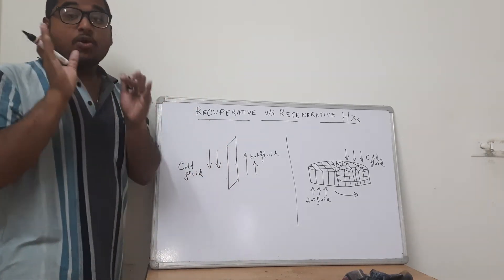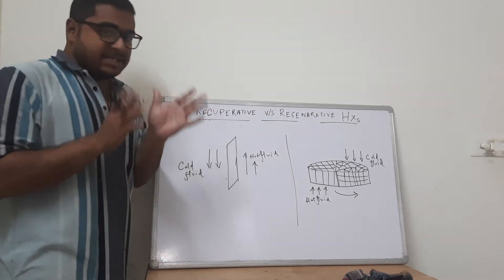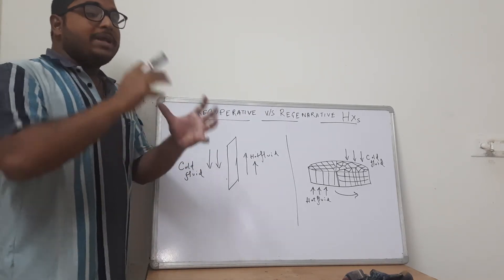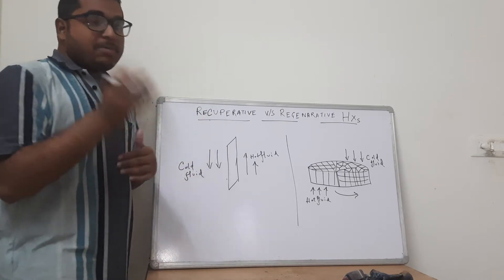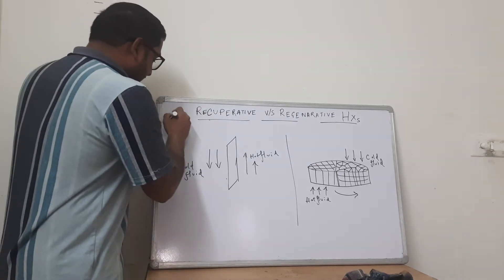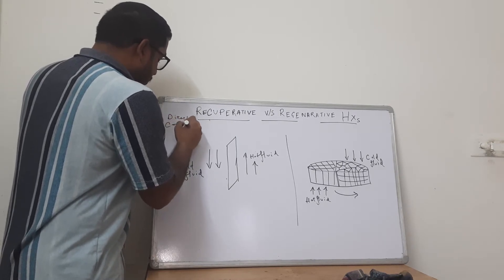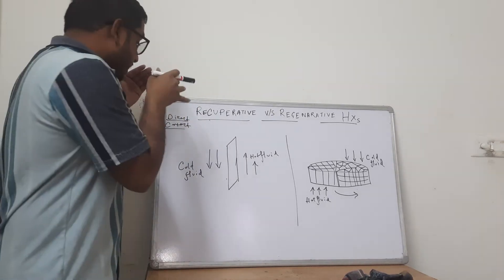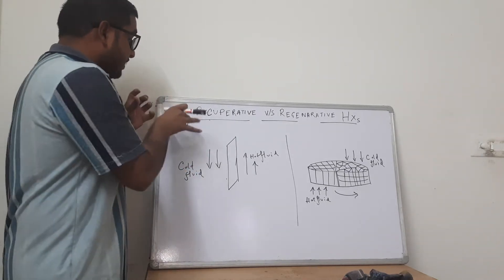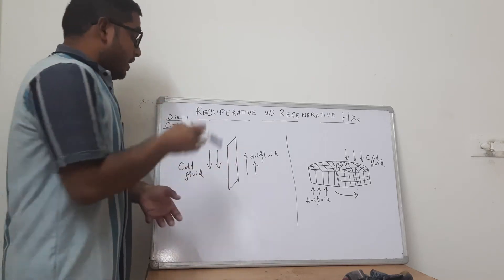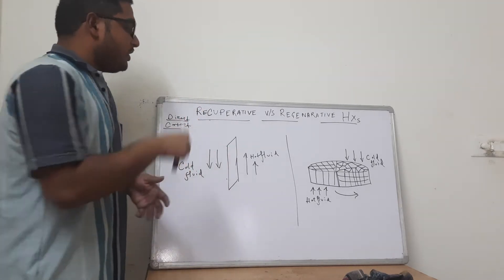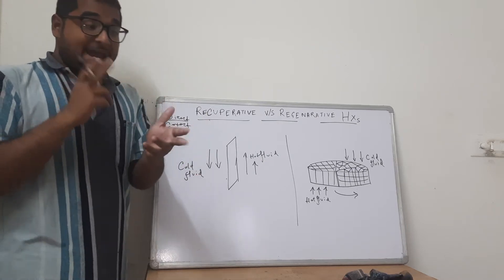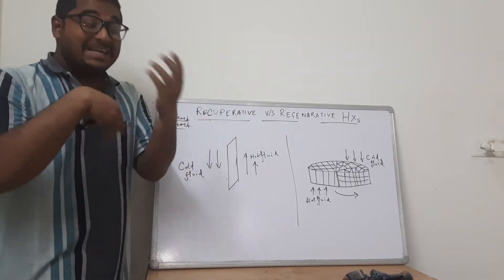When we discuss the contact of the hot and cold fluid in heat exchangers, there are three basic types. One is the direct contact heat exchanger, wherein the hot fluid is directly mixed with the cold fluid and therein occurs mass transfer as well as heat transfer. Direct contact type heat exchangers are not generally used in the industry because heat exchangers primarily should include heat transfer and not mass transfer. If the hot fluid is made to come in direct contact with the cold fluid, there is a probable chance of mass transfer along with heat transfer.